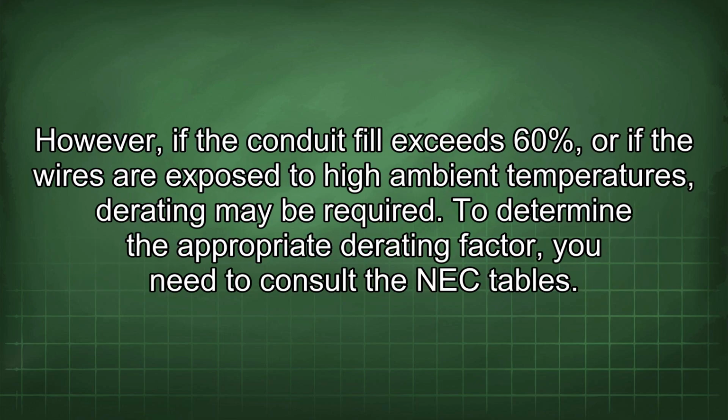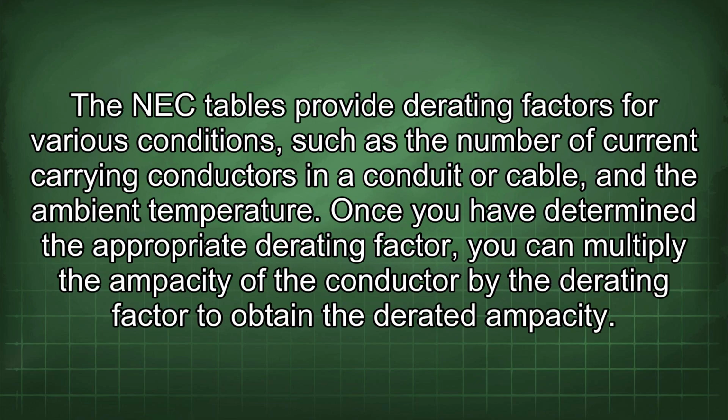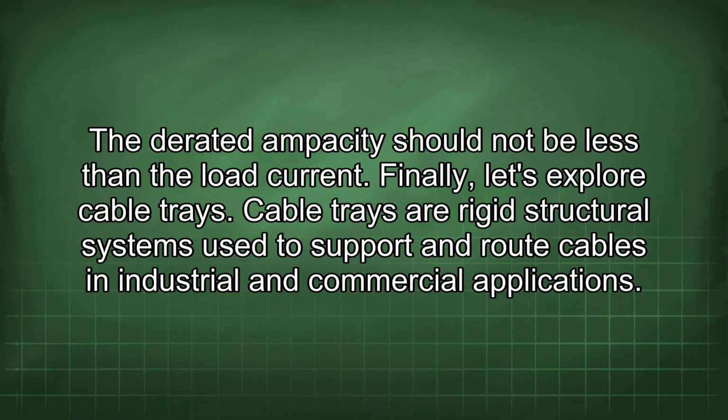However, if the conduit fill exceeds 60%, or if the wires are exposed to high ambient temperatures, derating may be required. To determine the appropriate derating factor, you need to consult the NEC tables. The NEC tables provide derating factors for various conditions, such as the number of current-carrying conductors in a conduit or cable, and the ambient temperature. Once you have determined the appropriate derating factor, you can multiply the ampacity of the conductor by the derating factor to obtain the derated ampacity. The derated ampacity should not be less than the load current.